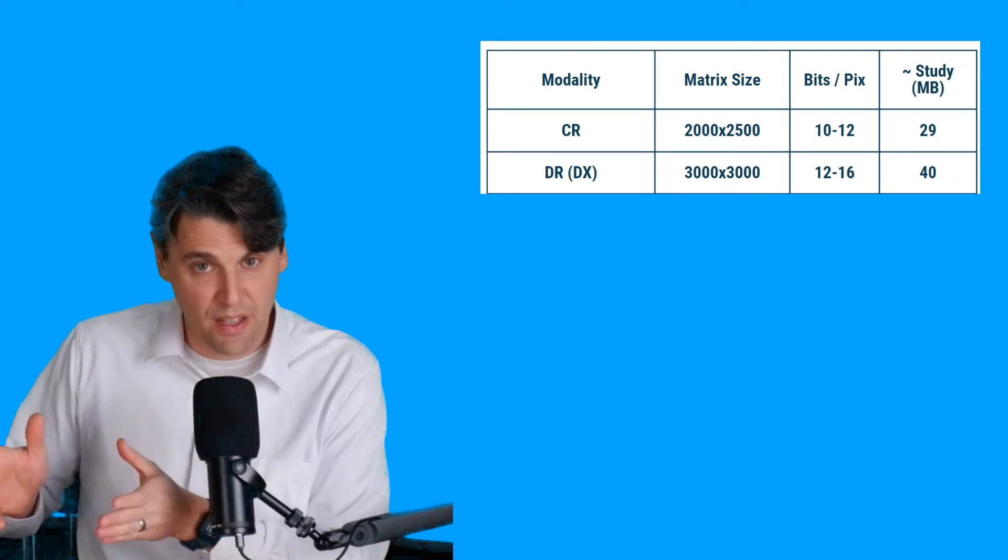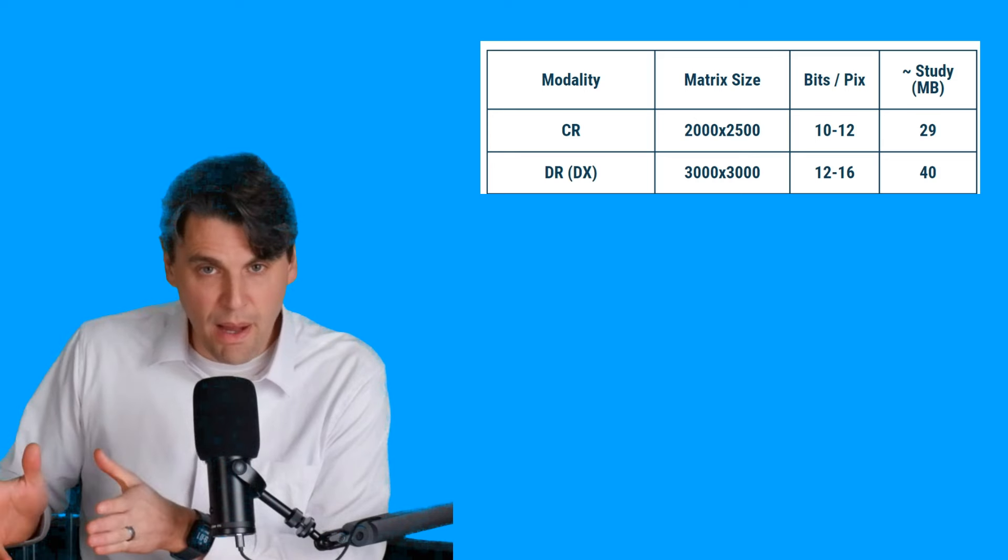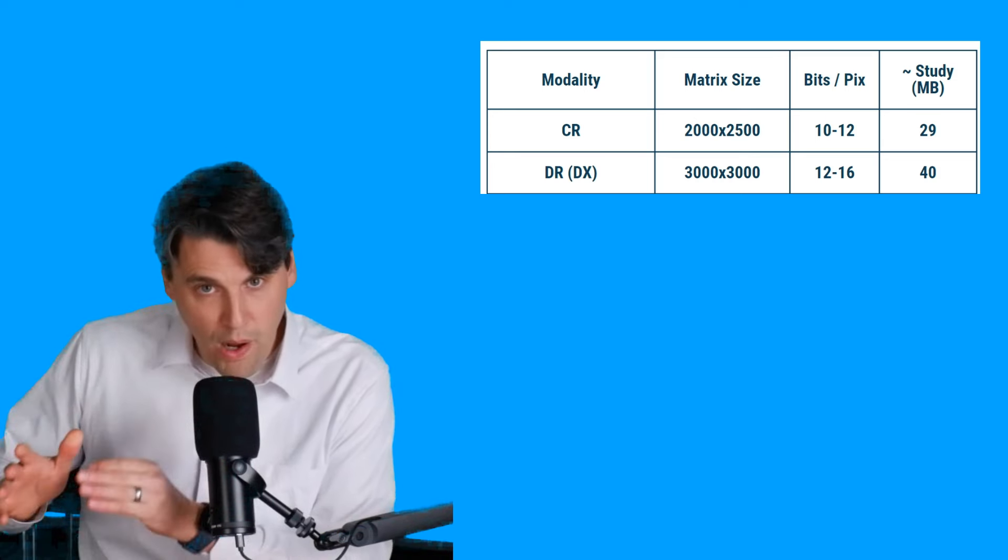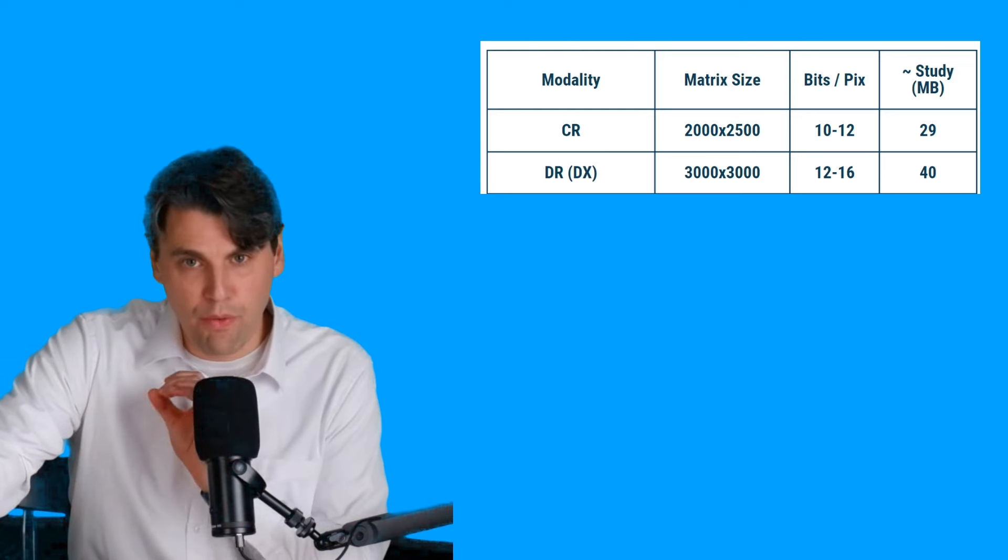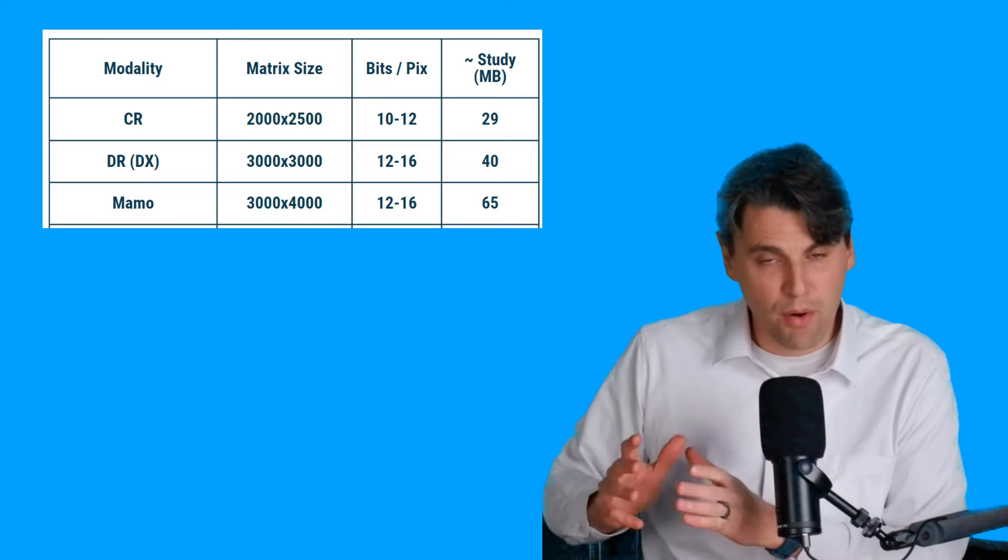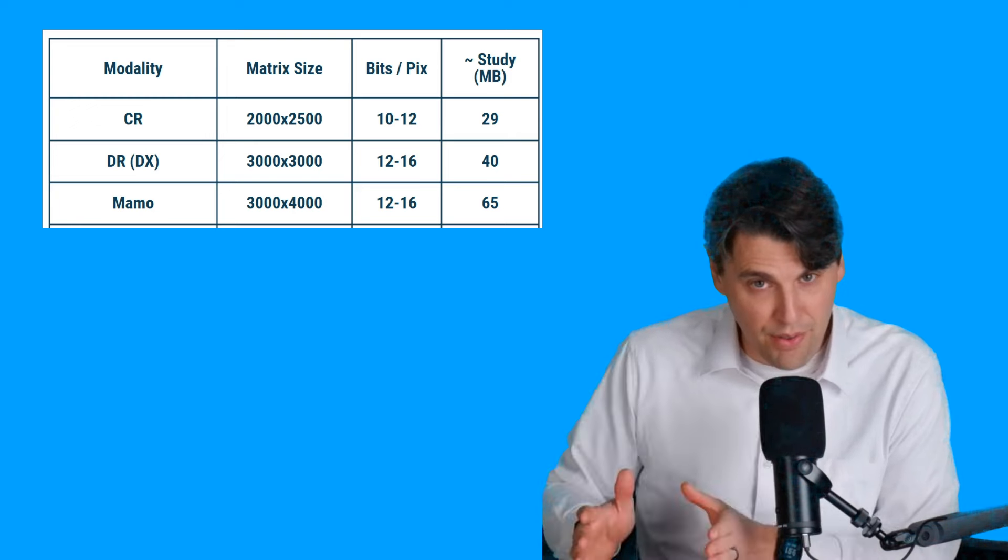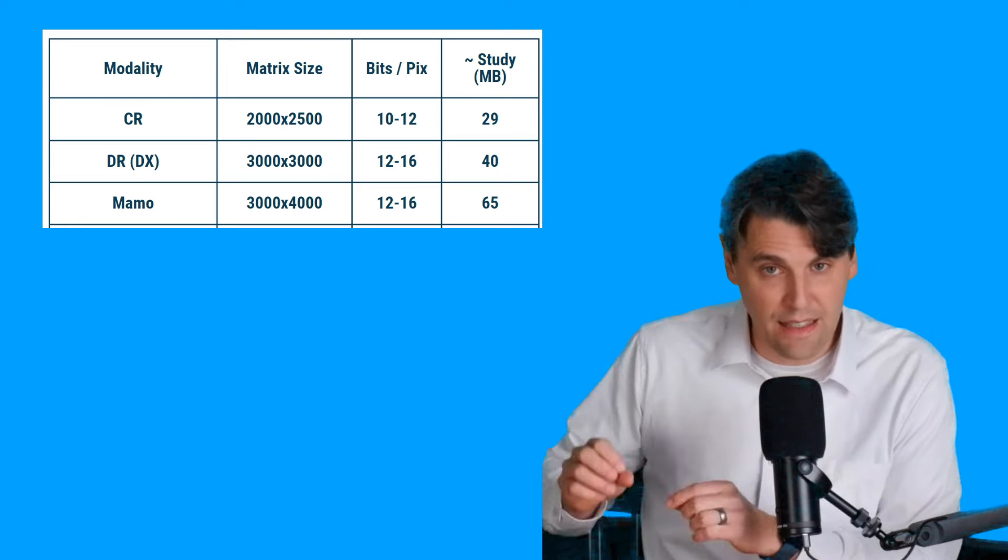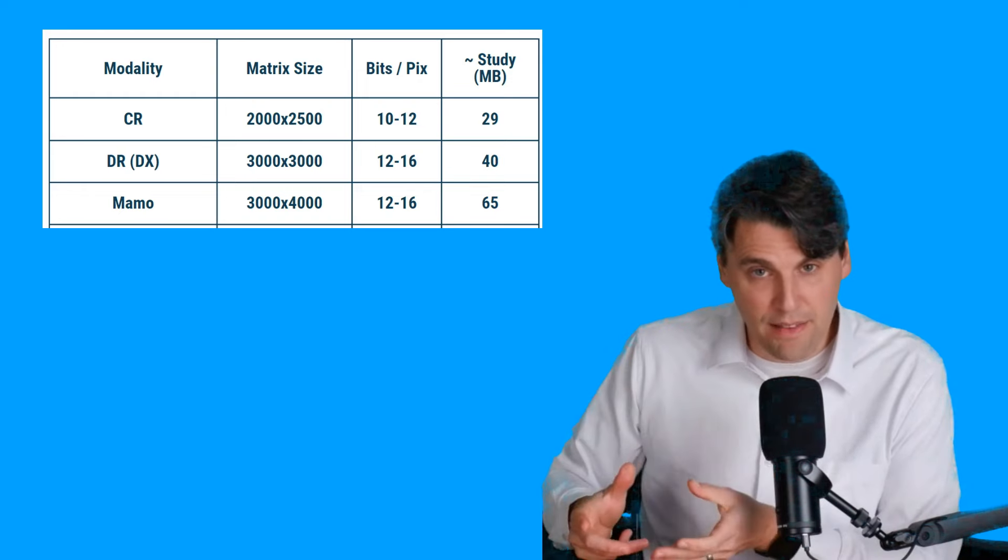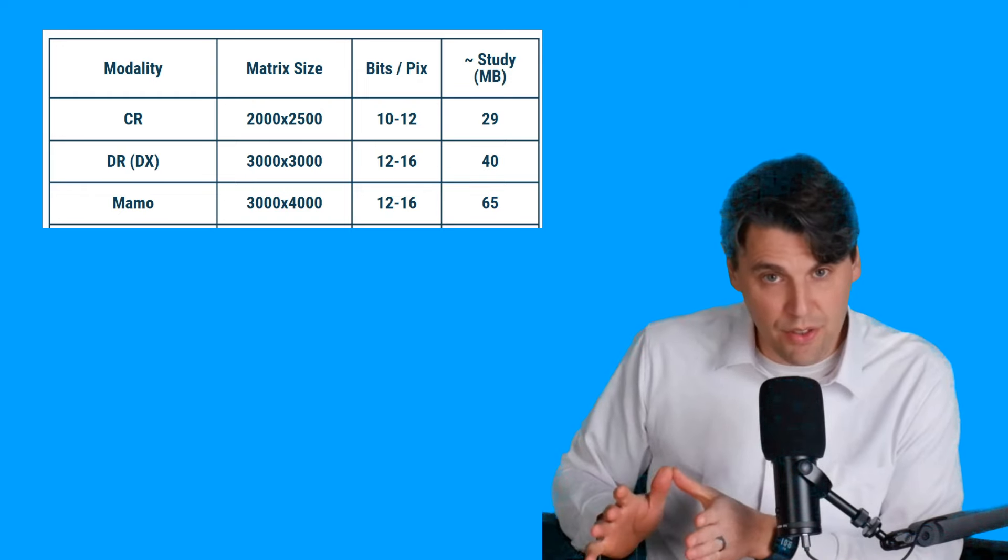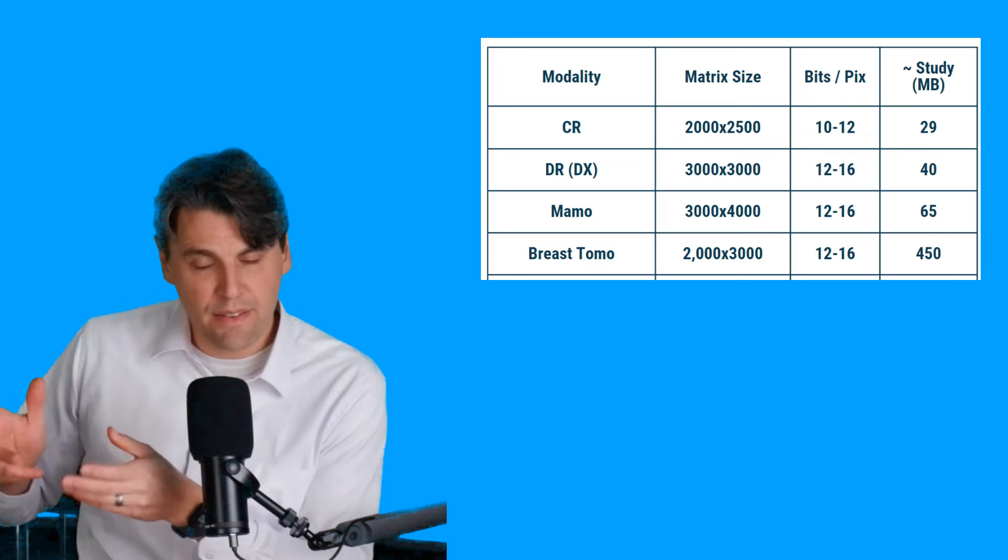Then for your DR or DX system, a typical digital x-ray system, matrix might be slightly larger, about 3000 by 3000, 12 to 16 bits per pixel. That's going to give you about 40 megabytes. The mammo goes up a little bit more at about 3000 by 4000 because resolution matters the most there, about 12 to 16 bits per pixel. So you're at about 65 megabytes per a given average study.